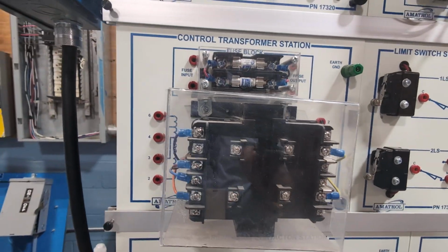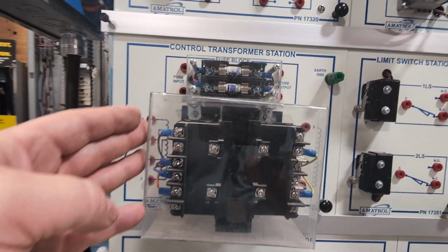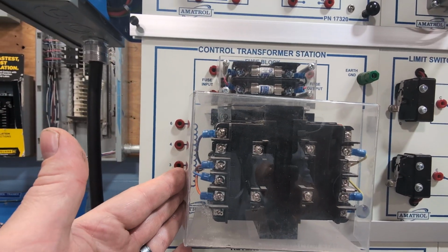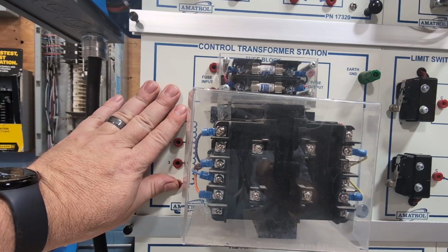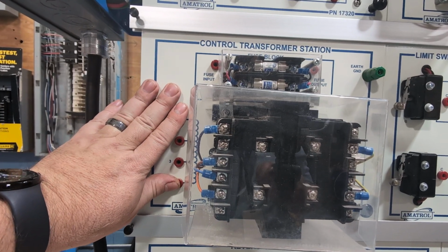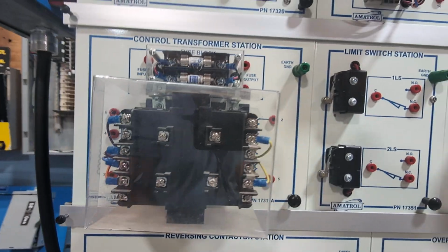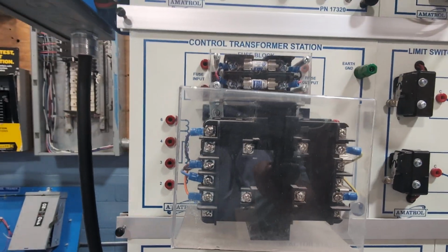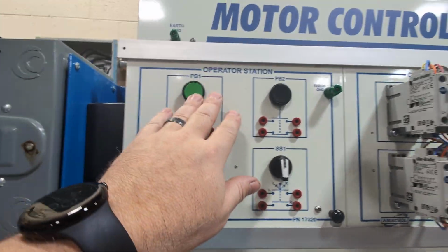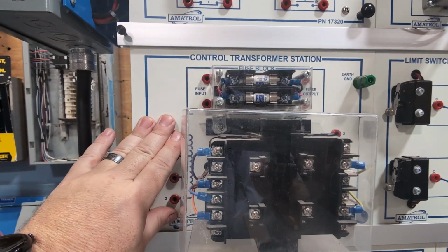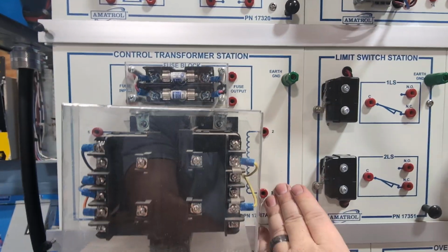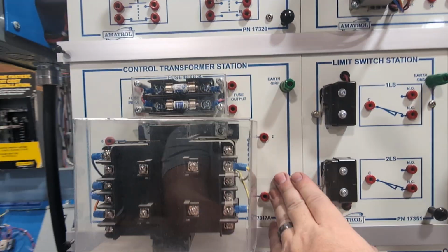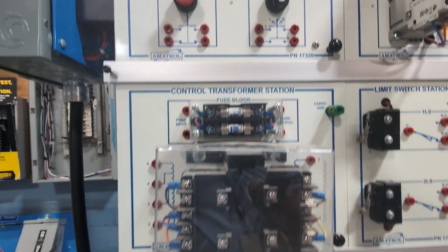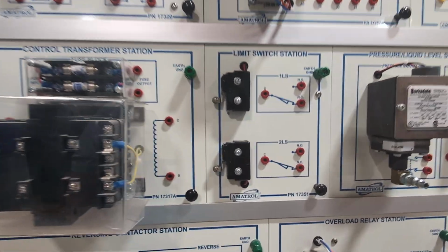Let's continue. This is the control transformer station. What's the purpose of a control transformer station? You put your high voltage here, 575, 600 volts, 230, whatever. High voltage here and low voltage out. The purpose of that is I want these controls to be low voltage. I don't want any high voltage in these. So in some industries it'd be 575 to 120, 575 to 24 volts. 24 volts is safe. We can work on 24 volts without getting hurt.